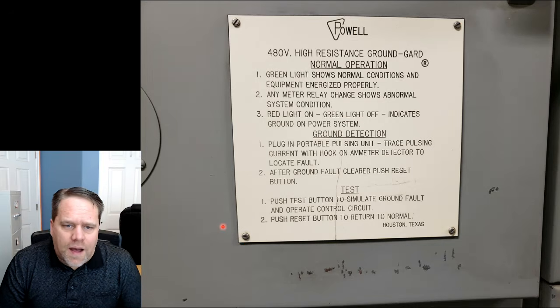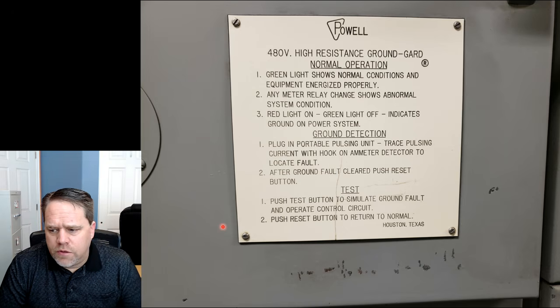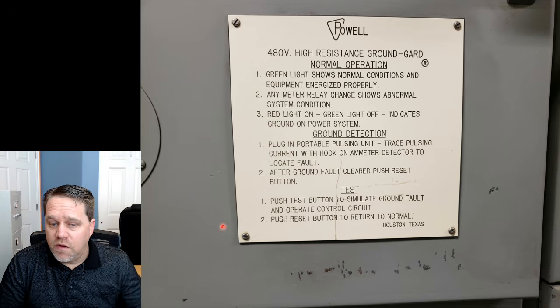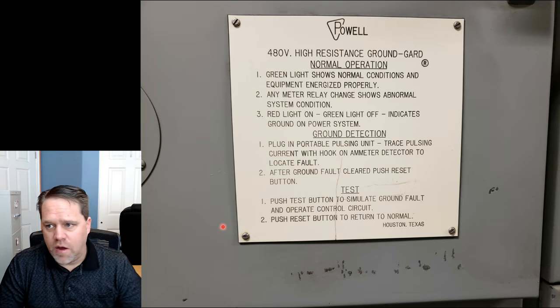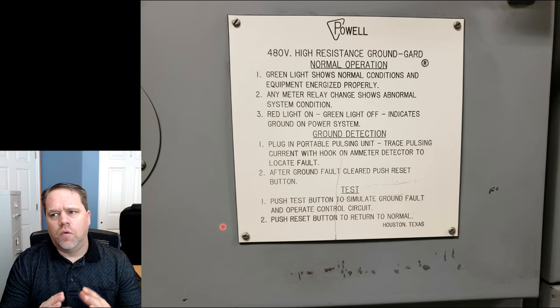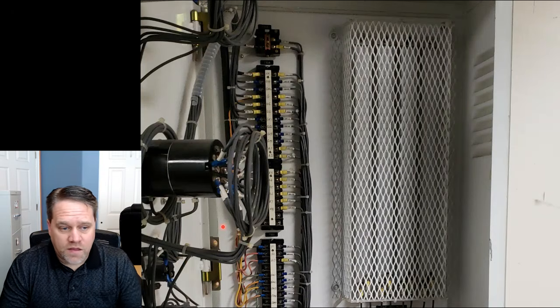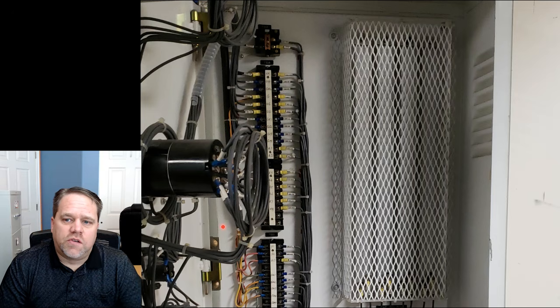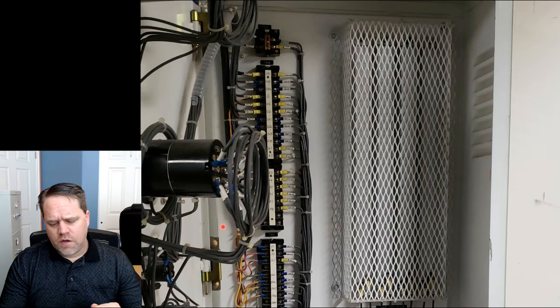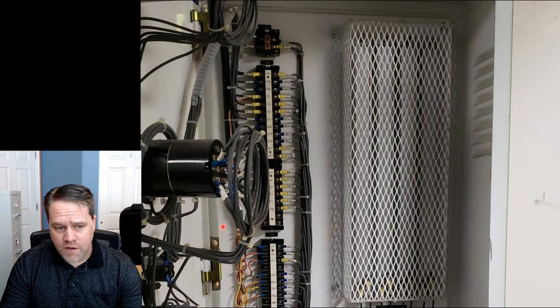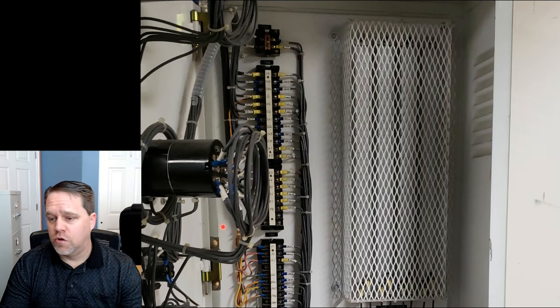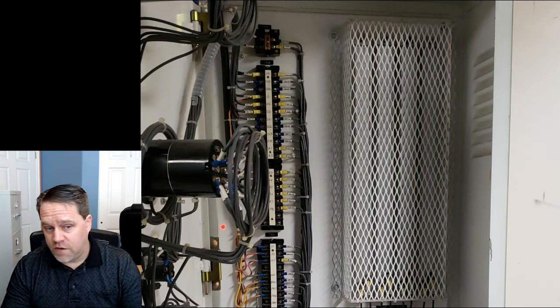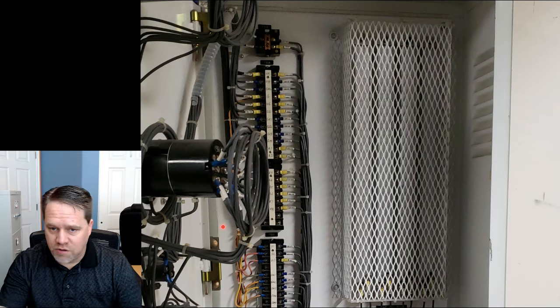We've also got high impedance grounding systems all through the 480 volt equipment in the power station. If you're not familiar with high resistance grounding or high impedance grounding, the idea is that you insert a resistor, and that's what that white thing is here in the picture. You put a resistor in the system at the transformer. So this is a three-phase Y-connected system. There's no neutral. It's a Y system, but there's no neutral. There's a neutral point. The XO is a neutral point, but you don't have a neutral conductor that leaves it.